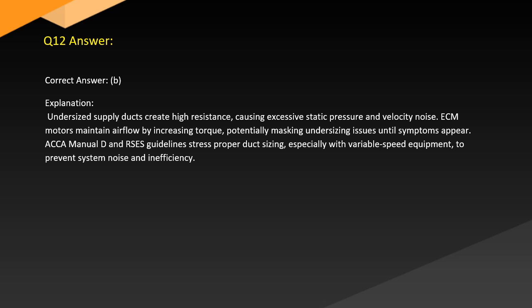Answer. Correct answer: B. Explanation: Undersized supply ducts create high resistance, causing excessive static pressure and velocity noise. ECM motors maintain airflow by increasing torque, potentially masking undersizing issues until symptoms appear. The ACCA Manual D and RSES guidelines stress proper duct sizing, especially with variable speed equipment, to prevent system noise and inefficiency.